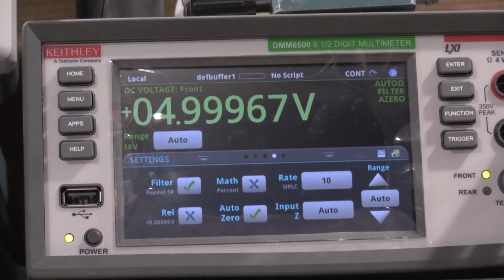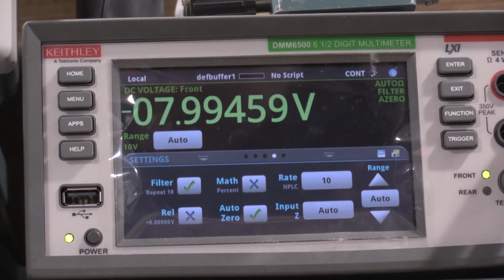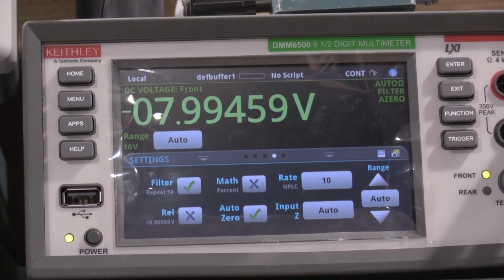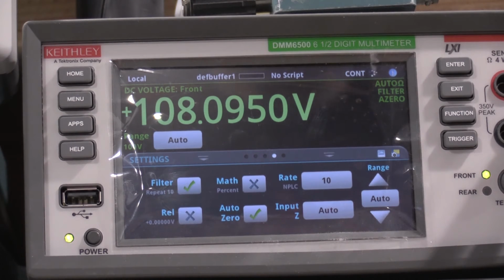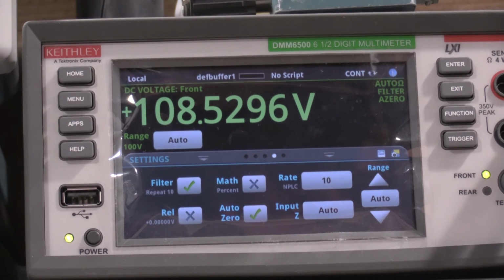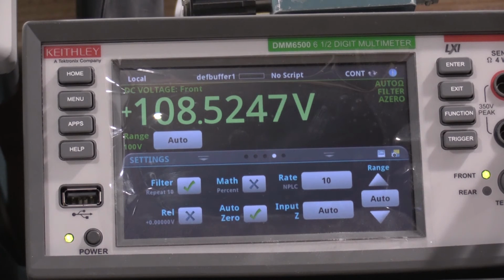Because it's set so slowly, I'm giving the meter a couple of times to stabilize. Next is -8. And I'm allowed 1.7%, so 7.86 to 8.14. Perfect. And plus 110. You guys can see what I'm waiting on as it counted up, because the first time it read 40, then it read 108. So I'm allowed 106.7 to 113.3, plus minus 3%. We're at 108. That's perfect.